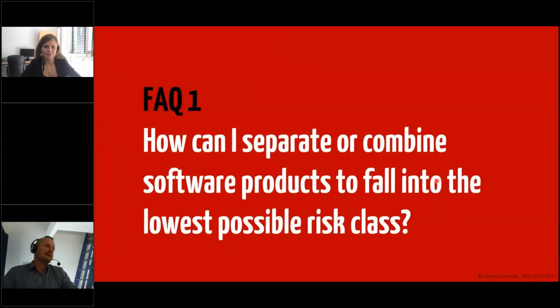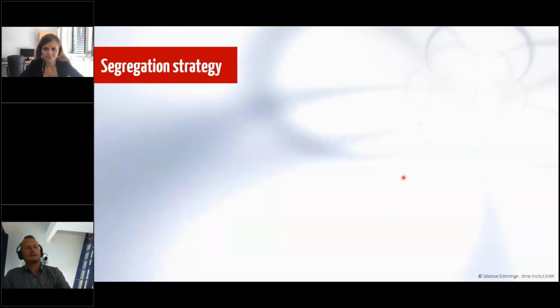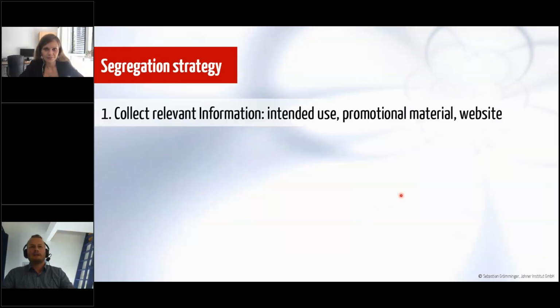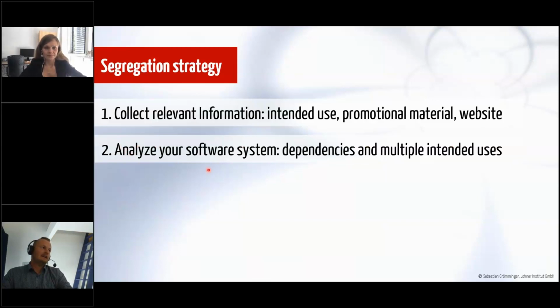Okay. I can go into details for those FAQs. For instance, this is the most severe one: how can I separate or combine software products to fall in the lowest possible risk class? And there it's necessary to have a segregation strategy. So I give you a four-step protocol on how to segregate. First of all, collect relevant information. Take the intended use, and if you don't have one, write one. Look into your promotional material and your website, what your claims are already, and then analyze your software system and look at the dependencies and the multiple intended uses.